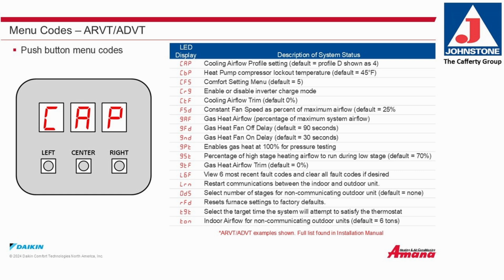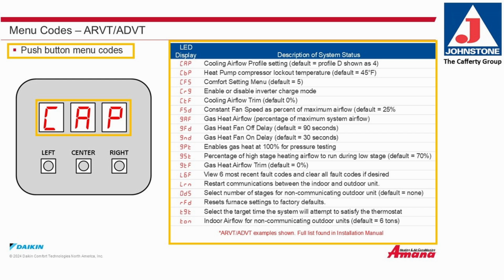Menu codes. Push-button menu codes. CAP, Cooling Airflow Profile Settings. Default is Profile D, shown as 4. CBP, Heat Pump Compressor Lockout Temperature. Default temperature, 45 degrees Fahrenheit. CFS, Comfort Settings Menu. Default 5. CRG, Enable or Disable Inverter Charge Mode. CTF, Cooling Airflow Trim, Default 0%.